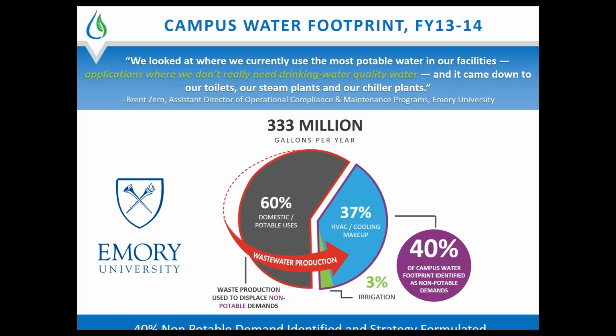This was Emory's water budget for the year. So about 60% of water on campus is used for potable applications, and about 40% of water on site is used for non-potable applications. This is pretty typical of most campuses that we see in the southern portion of the U.S. It's also typical that the split between heating and cooling water use and irrigation is quite pronounced, as it is here. Irrigation tends to be one of the more visible uses of water, but typically for a district-based treatment system, heating and cooling make up significantly larger amounts of flow. So in general, there's plenty of sewage, that 60% of domestic use, available to treat to meet the non-potable demand. Next slide, please.